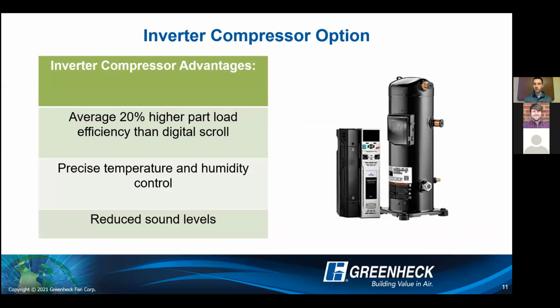Again, thinking about those part load conditions, not at full capacity, we want to make sure that we're turning down that motor speed to save energy. You also get this saving, but still having precise temperature and humidity control, and it still has really good turn down as well. And then that third benefit is reduced sound levels. I'm not sure if anybody's ever heard of digital scroll load and unload, but a lot of calls that we get from the service side of things, they ask if our compressor is broken, or they're calling to see what's wrong with it because they think that loading and unloading sound means something is happening. In all reality, it is just a pretty obnoxious sound that will cause a lot of noise concerns if you are in those noise critical applications.